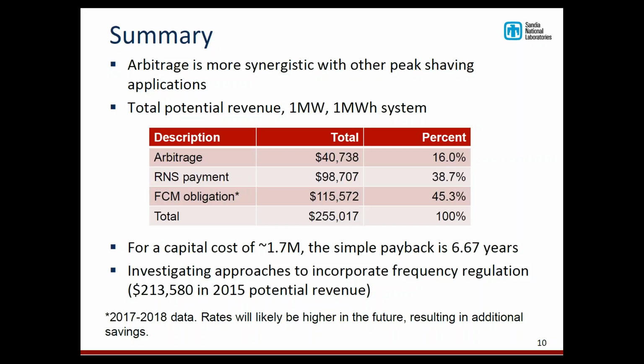So right now we're looking at some approaches to incorporate frequency regulation. For example, in 2015, it was around $200,000 in potential additional revenue. But because it is contrary to the two peak shaving applications related to the RNS and FCM obligations, we're going to have to do a little bit more analysis to harvest that additional revenue. But the great news is there are plenty of opportunities for revenue, and for a capital cost of, say, $1.7 million, you'd get a simple payback of about 6.5 to 7 years. So like Todd said earlier, these are some of the best numbers that we've seen for any application.